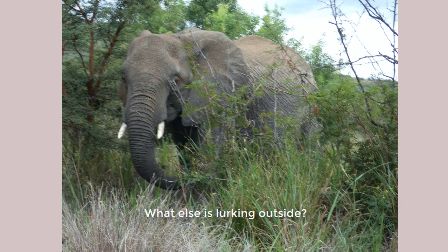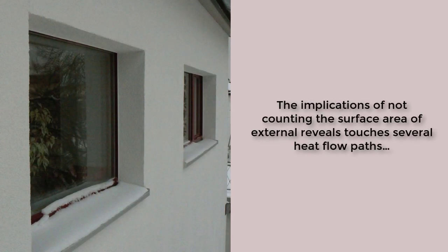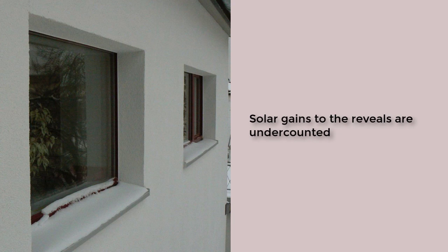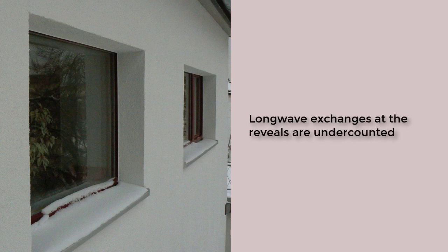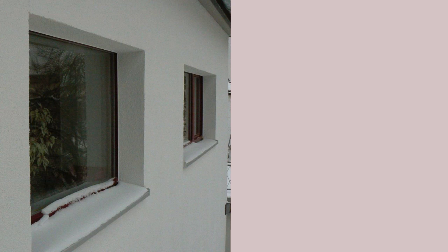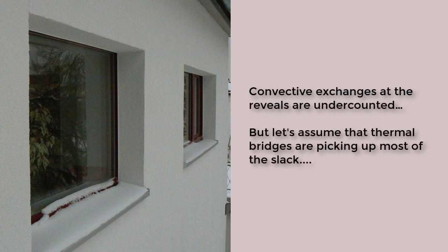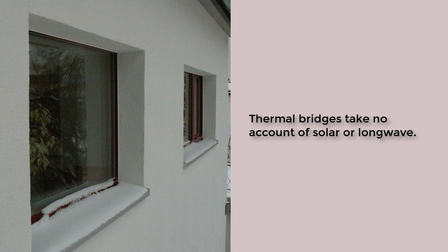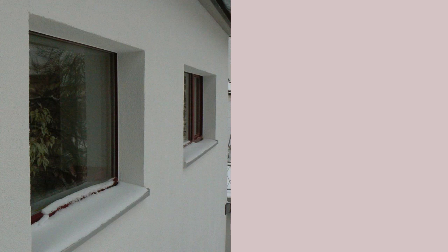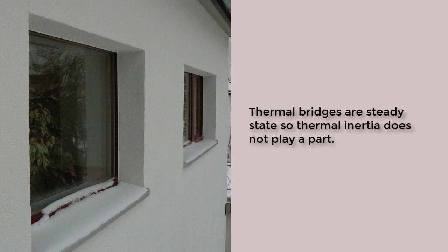The elephant outside the room — that's external reveals. Going beyond treating reveals only in terms of shading, there's a host of other heat transfer factors that are realistically getting undercounted. Sunlight falling on the outside reveal? It's not there — it doesn't get counted; there are no surfaces for sunlight to reflect from. Long-wave radiant exchanges? They're not there — the glass probably sees a lot less of the sky. Convection exchanges at reveals? Thermal bridges sort of cover that, but thermal bridges don't know about sunlight falling on a reveal, or radiant losses from reveals, and lots of construction types have substantial thermal inertia — nothing that psi values take into account.